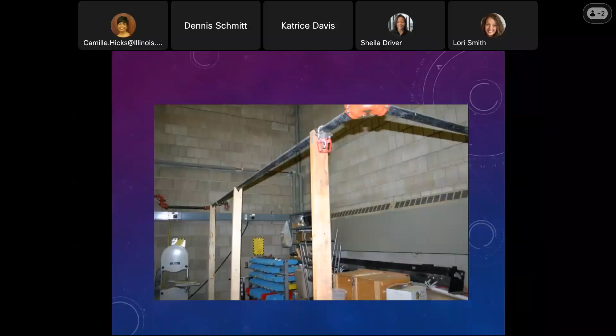This is just one that was crazy to us, actually from the city of New York. This is a sprinkler pipe for this area of the building, and they used 2x4s to support the sprinkler pipe from below, with all this storage happening behind it. These wood construction posts can easily be knocked out of place and damage the sprinkler system. All supports have to come from above or sidewall, so this is in violation, and it would be an automatic citation.